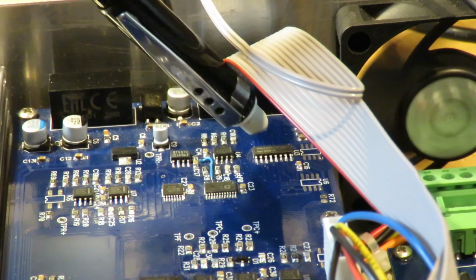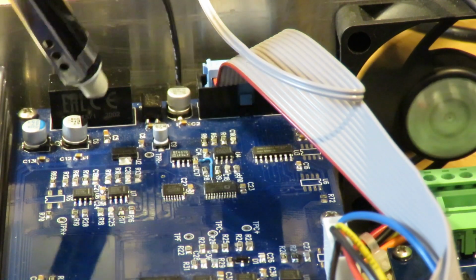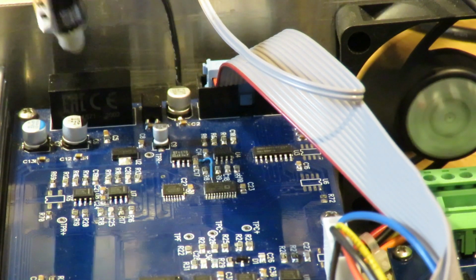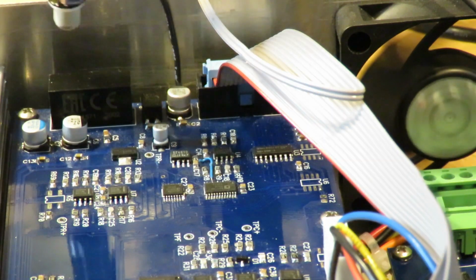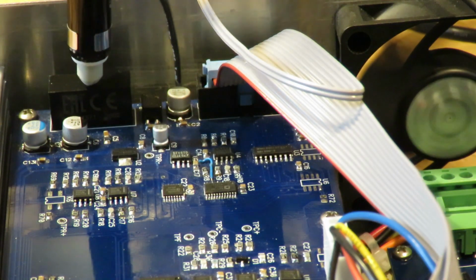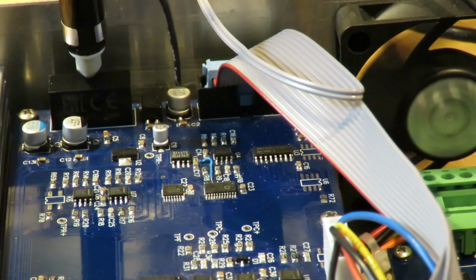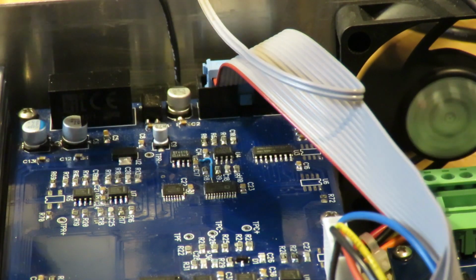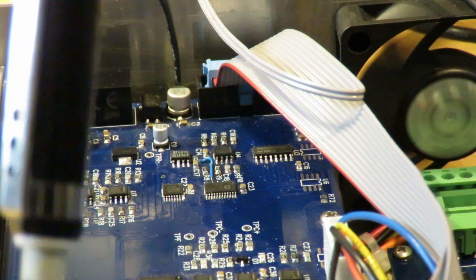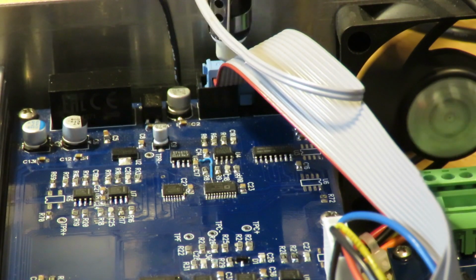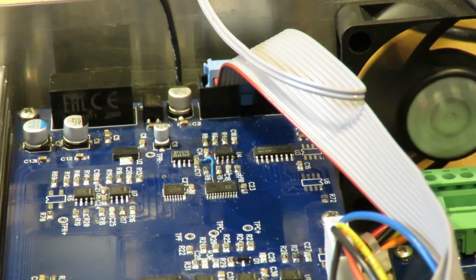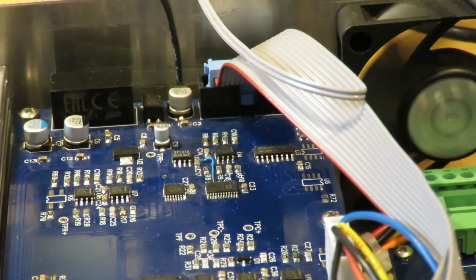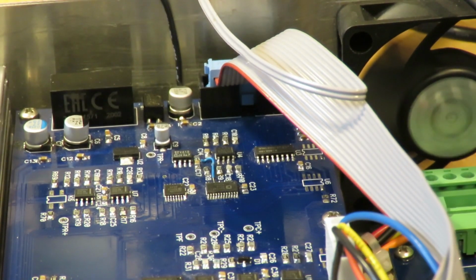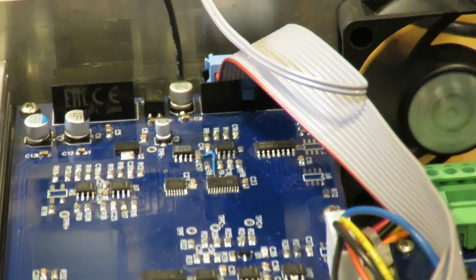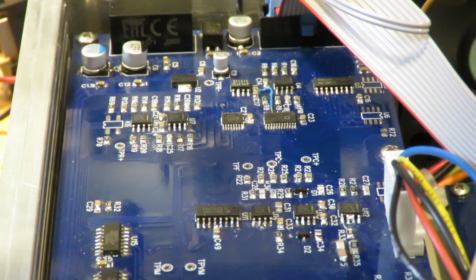There's the isolators. The DC to DC, which is this guy, a little 3-watt plus or minus 15 volt DC to DC, is also isolated. So it's an isolation barrier that runs through there. So the whole instrument is isolated except for the interface. All the analog circuitry for the instrument is fully isolated. A little bit of filtering.